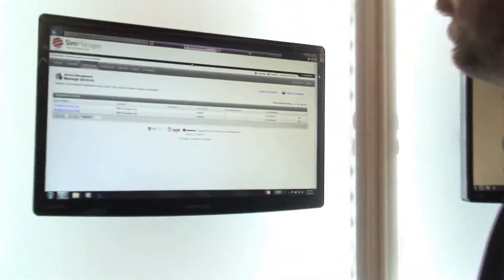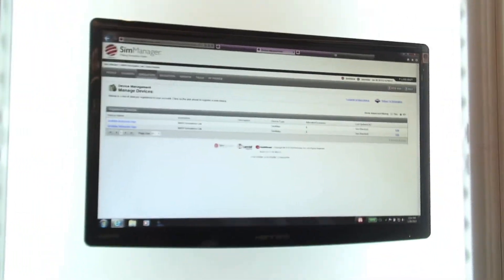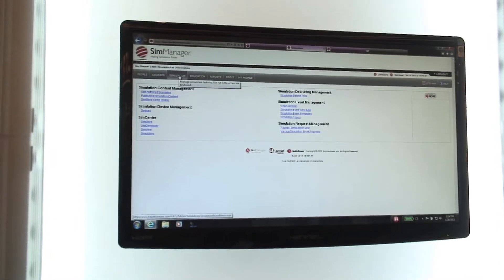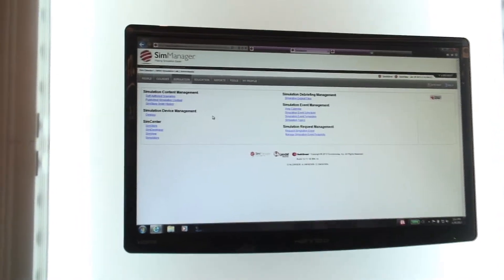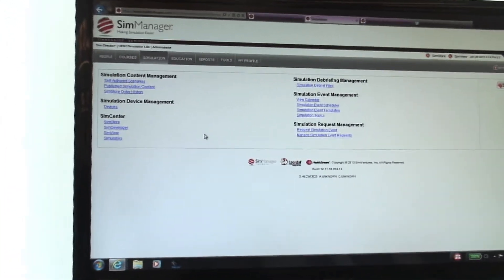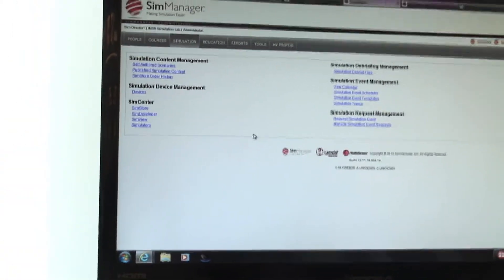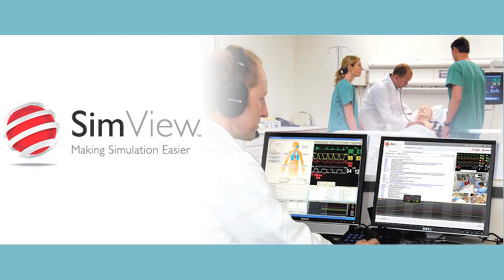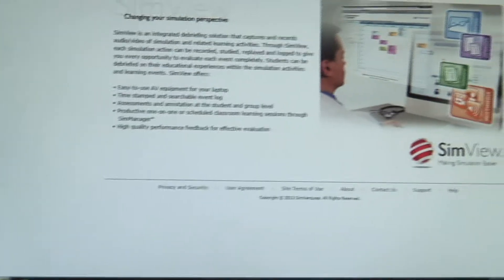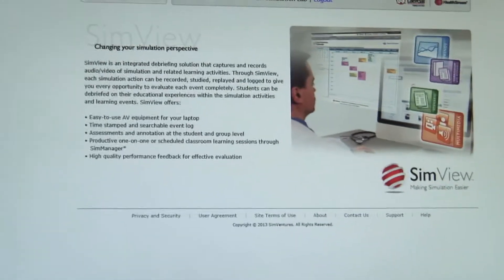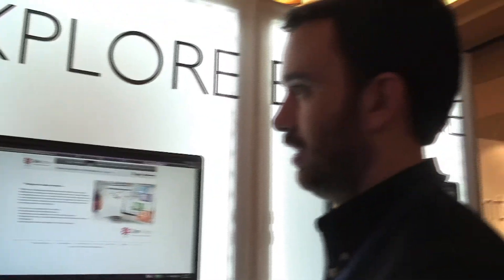But this is what it spits out, so basically you can see, just in the simulated 31 days of this month so far, we've used ALS simulator for five hours. Back in my day. Exactly. I have to do all this by hand if I really want to get that detailed. And hardly we would get down to the equipment level just because the task of performing the room in and of itself is enough. But this is very helpful to be able to see what pieces of equipment are really kind of key pieces of equipment and might be necessary for repair or additional maintenance or long-term purchase plans for technology refresh cycles.